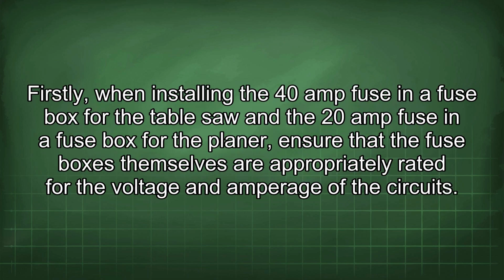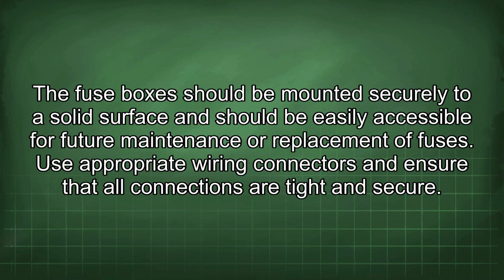Firstly, when installing the 40-amp fuse in a fuse box for the table saw and the 20-amp fuse in a fuse box for the planer, ensure that the fuse boxes themselves are appropriately rated for the voltage and amperage of the circuits. The fuse boxes should be mounted securely to a solid surface and should be easily accessible for future maintenance or replacement of fuses. Use appropriate wiring connectors and ensure that all connections are tight and secure.